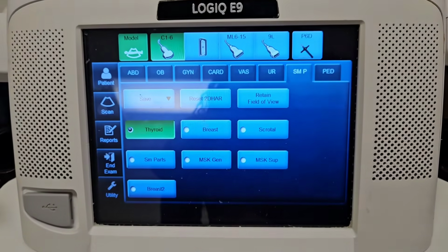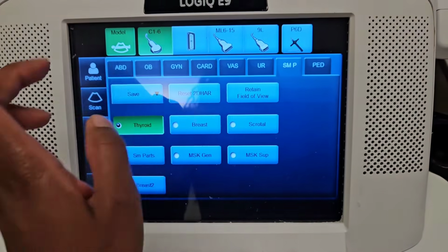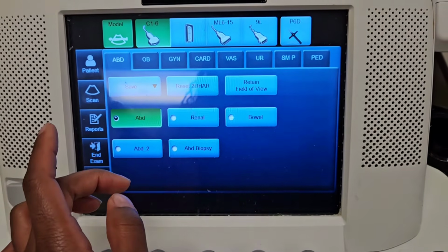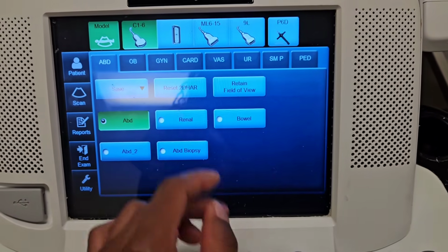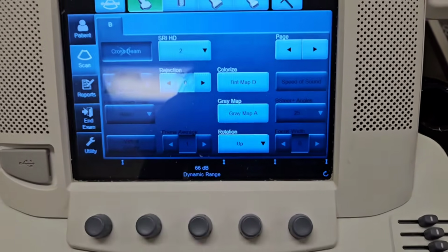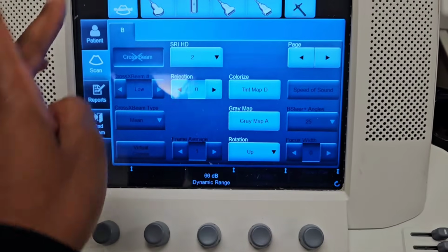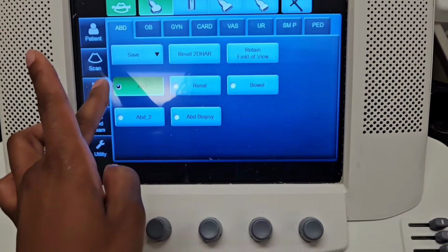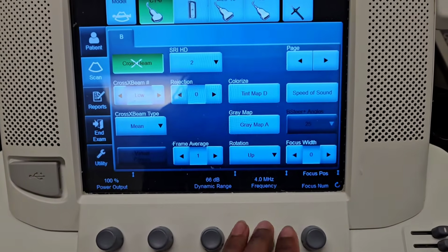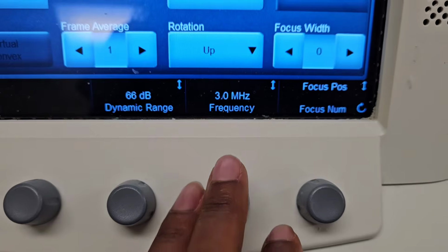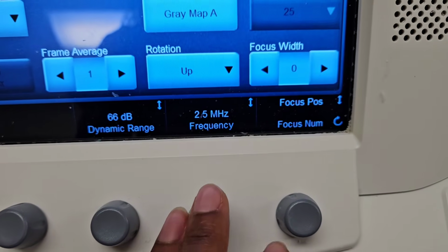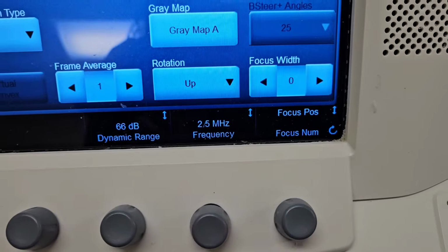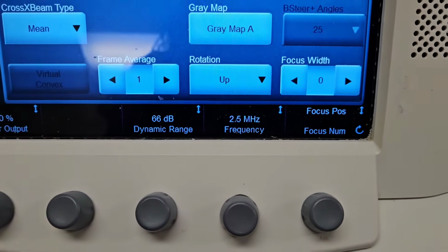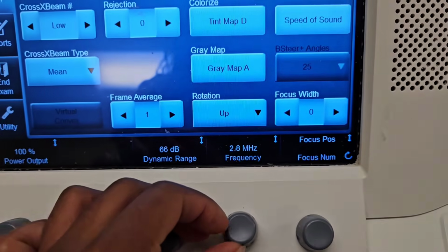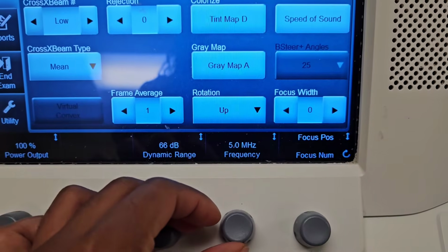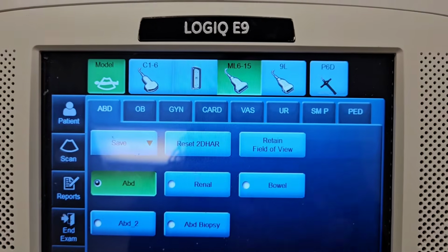Now let's check out the curvilinear transducer, the C1-6. 6 megahertz is not the only frequency at which this transducer can work. You can lower the frequency of this transducer, especially if you're working on a larger patient and you need better penetration. If you're trying to see the dome of the liver, you can lower that frequency all the way down to 2.5 megahertz. Now, if you are imaging a smaller patient or a more superficial abdominal structure, then you can keep that frequency up at 6 megahertz.